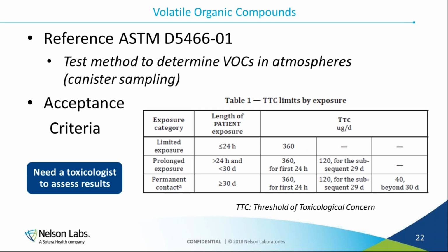The reason for that is the chemistry data you get is just a known amount of compounds, and for this it would just identify maybe so much alcohol or isopropyl alcohol, but we need to translate that back to the patient dose and determine if the amount of alcohol coming off the device is safe for the patient exposure. And so this TTC here listed is threshold of toxicological concern, and this is listed in the standard.